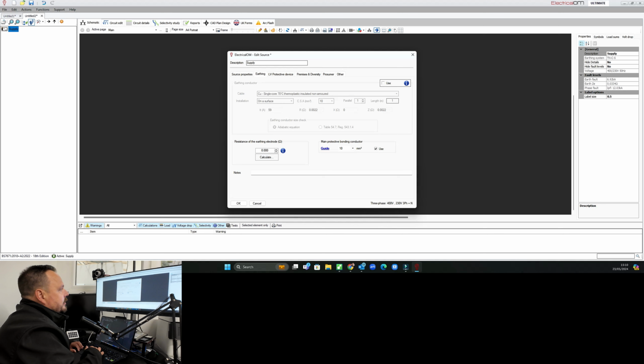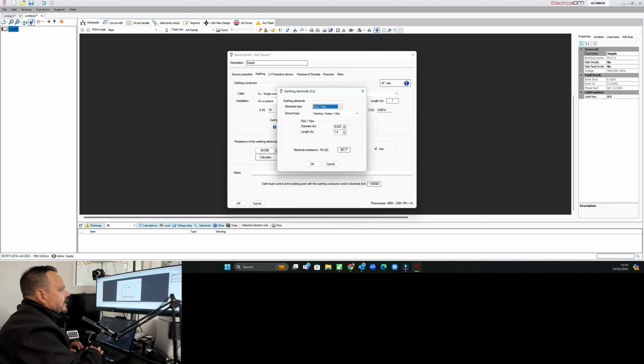Your earthing, so we're going to use the earthing conductor. It's just going to be a single core 16 mil, about a meter long. We can pop that in there. There will also be an earth electrode. So if we say the value of an earth electrode is going to be 40 ohms, you can calculate, and that will tell you the rod size you need, basically based on the ground conditions.